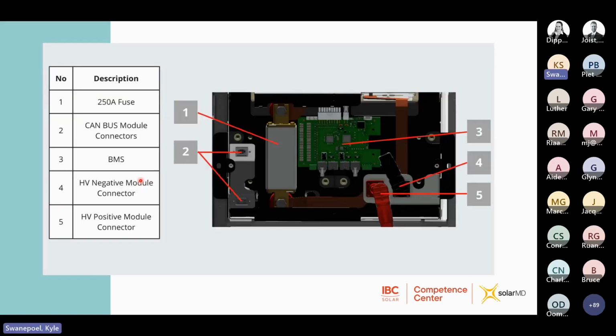Okay, and then just a front view. Yes, that's correct. And then each battery bank requires its own BMU. So you'll have one BMU per battery, and that battery will comprise anything from 8 modules, 14.3 kilowatt hour modules, up to 17 modules.